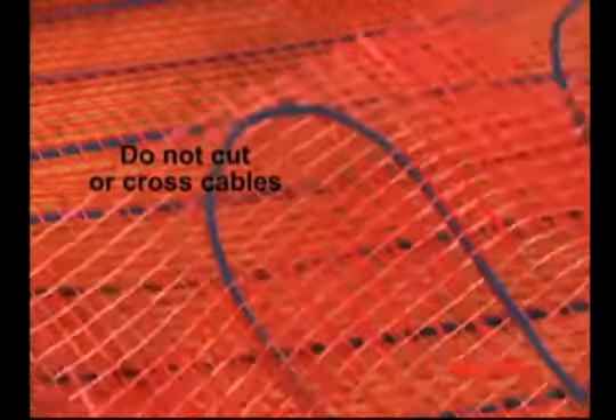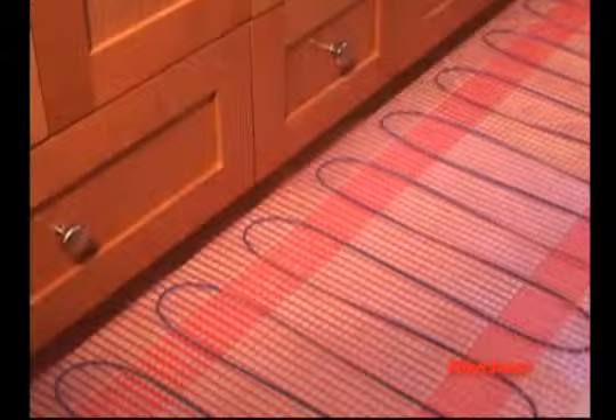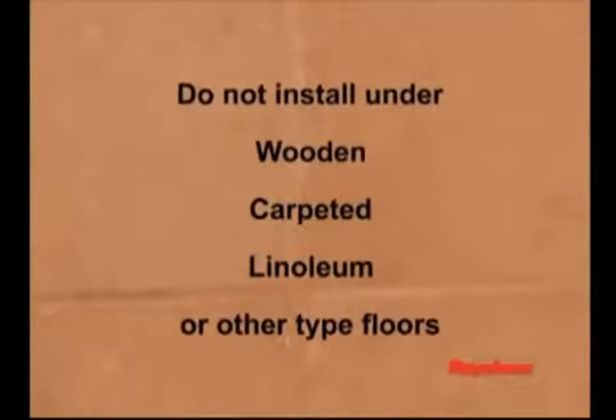The QuickNet heating cable cannot be cut, crossed over itself, or installed closer than the spacing in the mat. Note these important guidelines when installing the QuickNet mat. QuickNet mats are designed to be installed beneath ceramic tile or natural stone surfaces. Do not install beneath wooden, carpeted, linoleum, or other type floors. Be sure the subfloor is clean, rigid, level, and free of cracks.